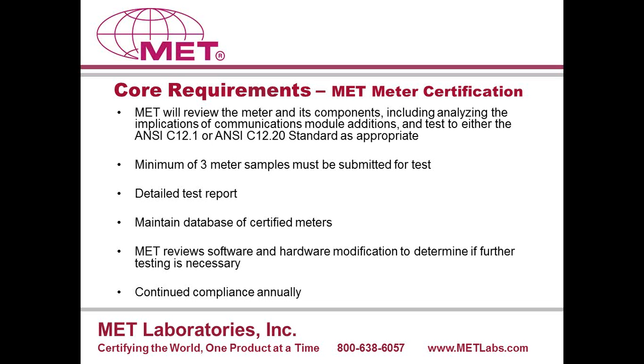So the core requirements for our meter certification program are, of course, that we need to test the required number of samples to the applicable tests out of either ANSI C12.1 or C12.20 as appropriate. To those standards, there must be a certain minimum number of meter samples tested as you run down through all the applicable tests. And what it boils down to is a minimum of 3 meter samples need to be tested for each of the tests.